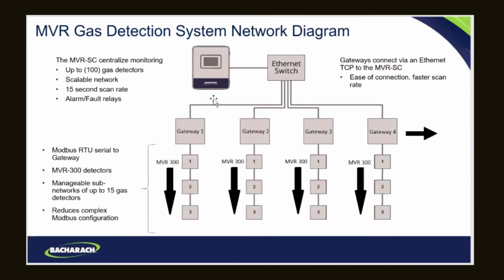So how many can we get on a gateway? Up to 15. So you're going to be sizing your network through the gateway, and then there are up to 15 of these MVR-300s on each one of the gateways. Okay. And these are going to add up to 100 as you go along that 8-port Ethernet switch.